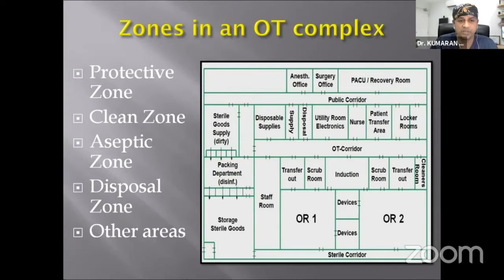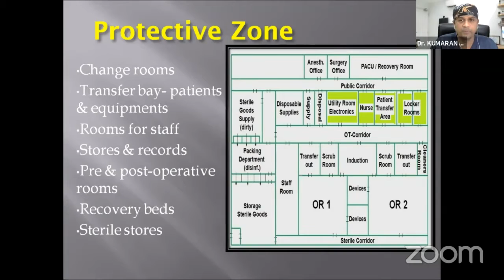So the protective zone is basically the zone where every person is allowed to enter with their street clothes. And if you're planning to have a restroom, it should be in this zone. It also consists of stores, post-operative and pre-operative rooms. The clean zone is basically an intermediate between the protective zone and the aseptic zone. You can incorporate the store room, the equipment, and the maintenance in these areas. The main area is called the aseptic zone, which is a sanctum sanctorum. You can also include the scrub room into this.